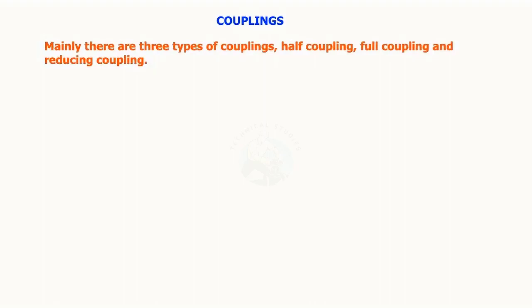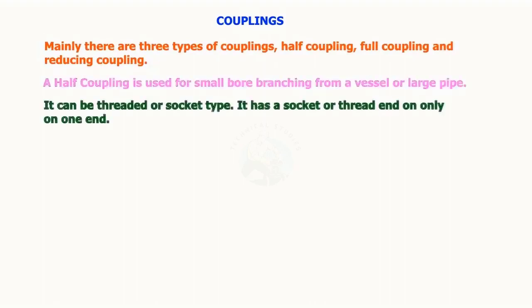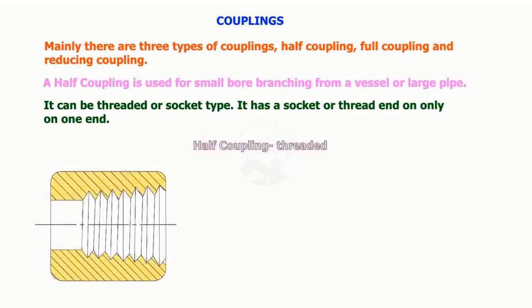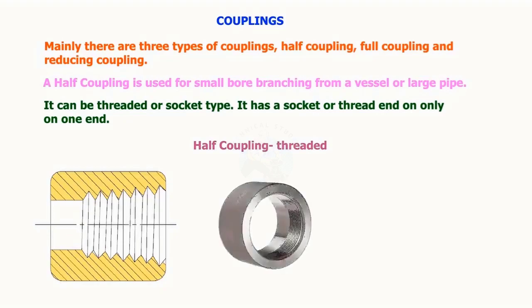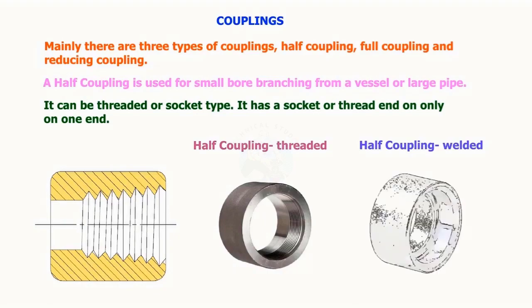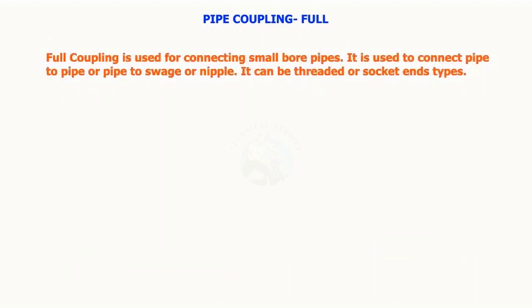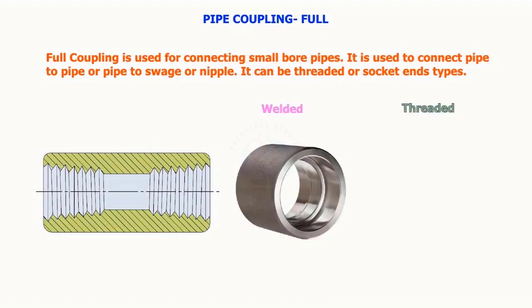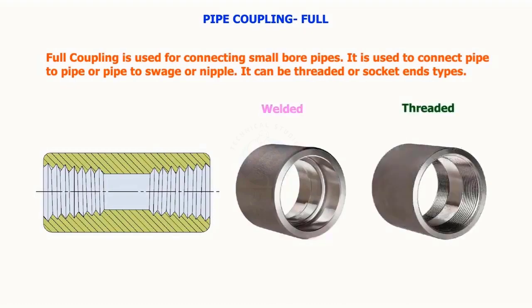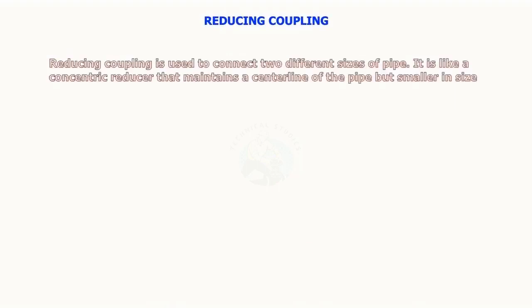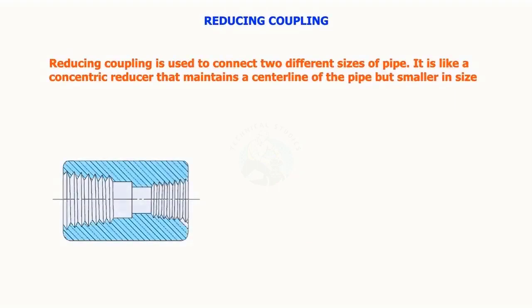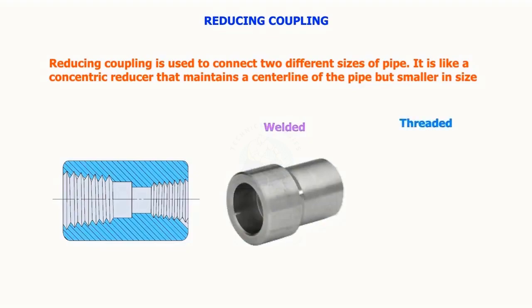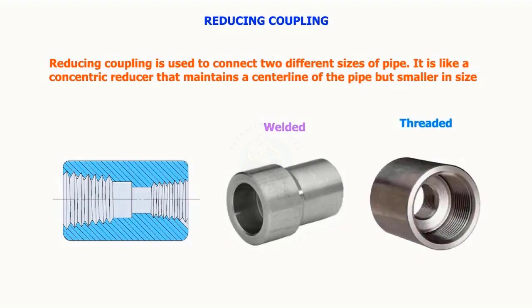Mainly there are three types of couplings: half coupling, full coupling, and reducing coupling. A half coupling is used for small-bore branching from a vessel or large pipe; it can be threaded or socket type and has a socket or thread on only one end. A full coupling is used for connecting small-bore pipes — pipe to pipe, or pipe to swage or nipple — and can be threaded or socket ends. A reducing coupling is used to connect two different sizes of pipes; it is like a concentric reducer that maintains the centerline of the pipe but is smaller in size.